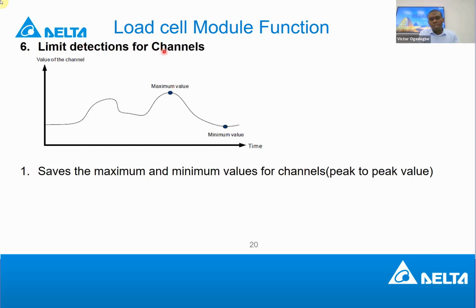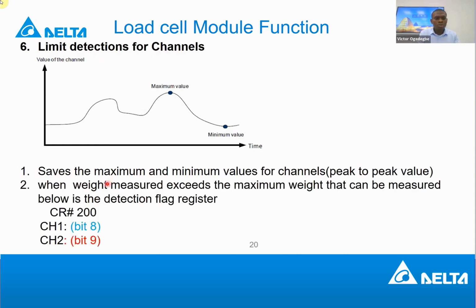You can determine the limits. Additionally, when the weight measured exceeds the maximum weight that can be measured, you have a flag to indicate that the weight I'm measuring is more than what I should measure. For example, the sensor I showed you is 5 kg. Its maximum is 5 kg, and I also set it as 5 kg in the module. If I measure 10 kg, this bit can give an indication that what is being measured is more than the maximum.